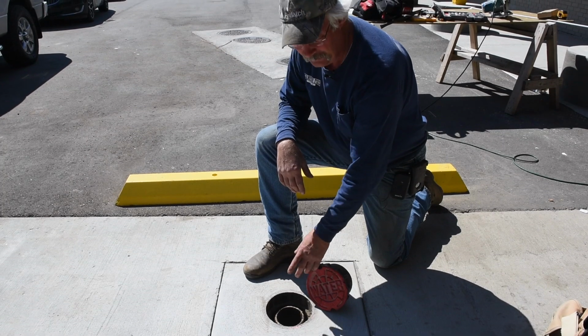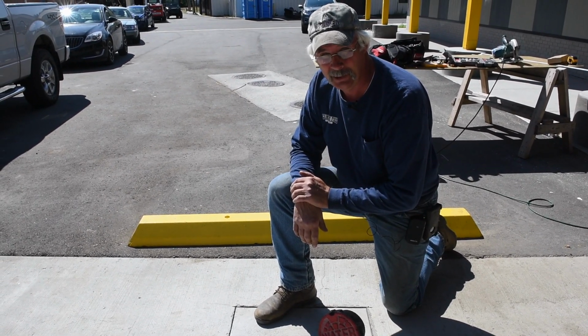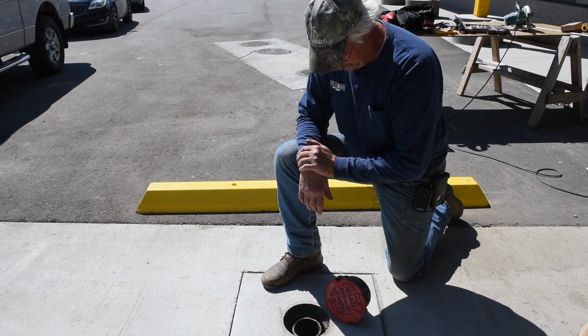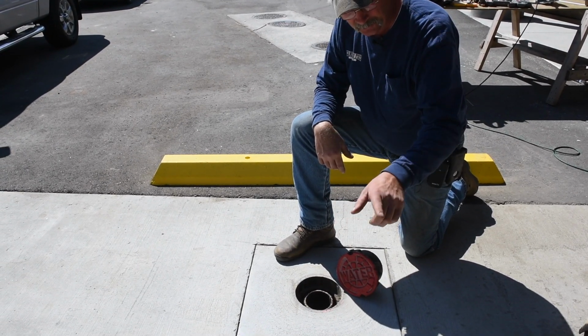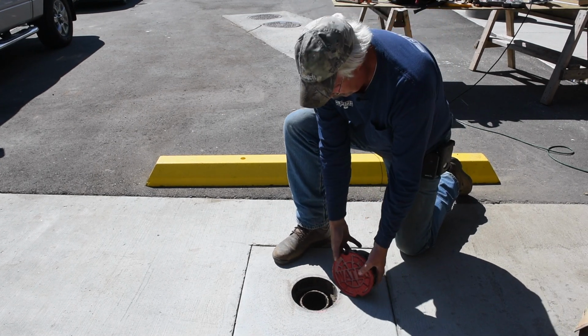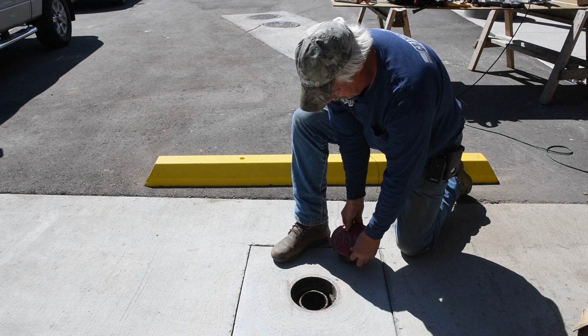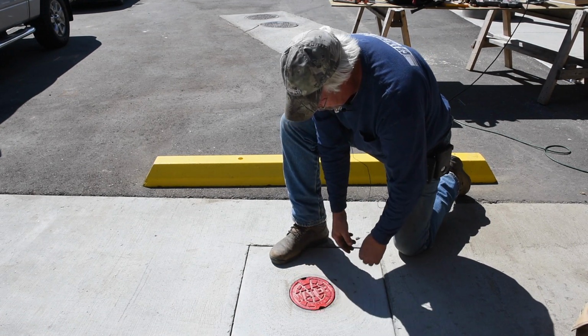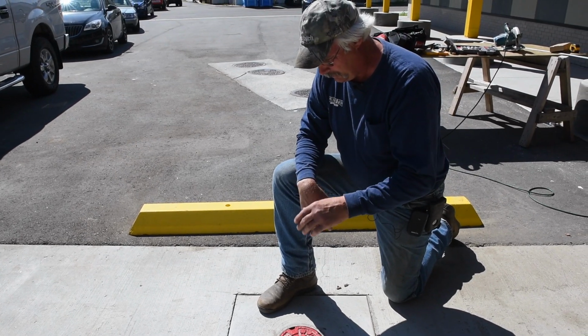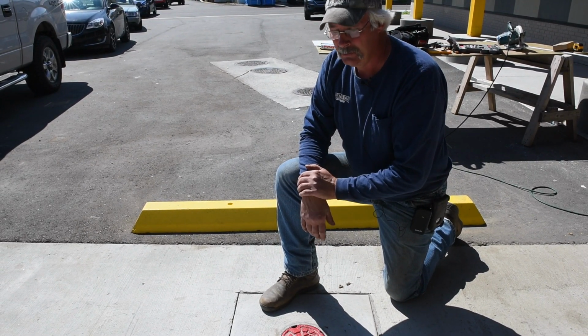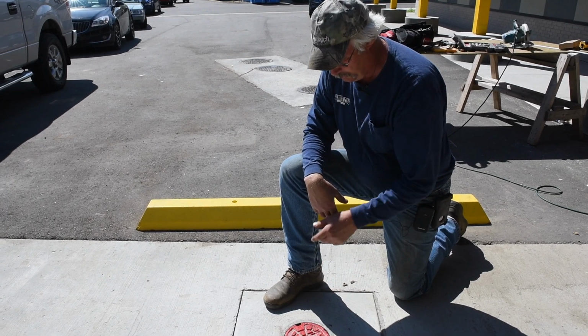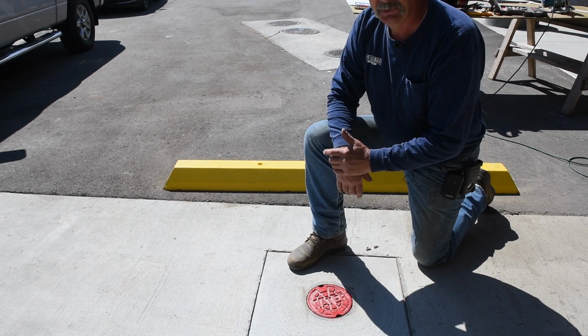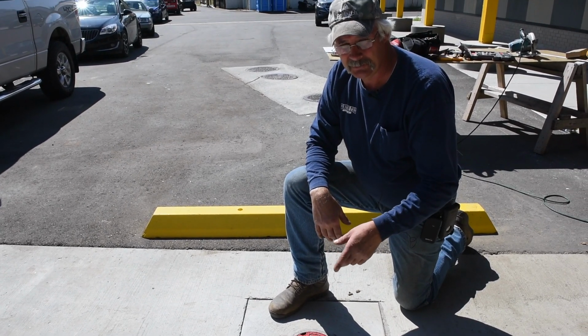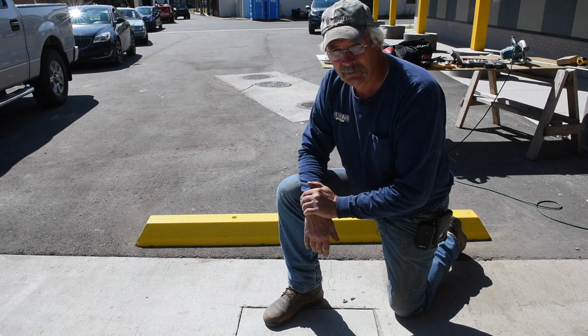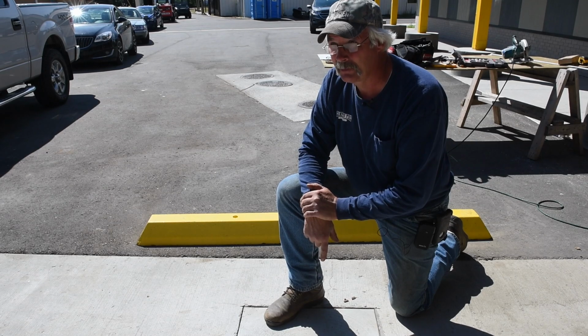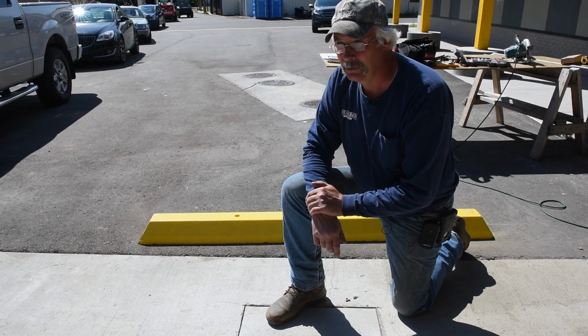This is your underground gate valve. There's a key just inside the south mechanical room hanging up in the unistrut on the right hand side. Open the door. So if you want to shut this underground coming off into this facility, you have to lift this cover out, drop the shaft down, turn it to the right, and it'll shut it off. So you got to make sure that's put back on. This is a loading dock area, so they didn't want to have a PIV right here. So we removed it, made it flush with the ground, and put a water cap on top of it. But this location here is approximately 15 feet straight out from the middle of the doors from the south mechanical room door. That's your underground shut-off coming from your underground into your facility on the south wing.